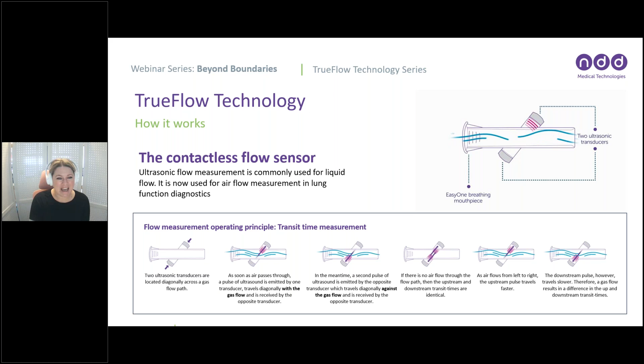So we broke down exactly how this measures in the chart that you see below. These two ultrasonic transducers are located diagonally across the gas path, most easily seen here on the EasyOn PC. As soon as the air passes through, the pulse of the ultrasound is emitted by one transducer and travels diagonally through the gas flow and is received by the opposite transducer. In the meantime, a second pulse of ultrasound is emitted from the opposite transducer, which travels diagonally against the gas flow and is received in the opposite transducer. If there's no airflow in the flow path, then the upstream and the downstream transit times are identical. As air flows from left to right, the upstream pulse travels faster and the downstream path travels slower. The result is the difference in these upstream and downstream transit times.